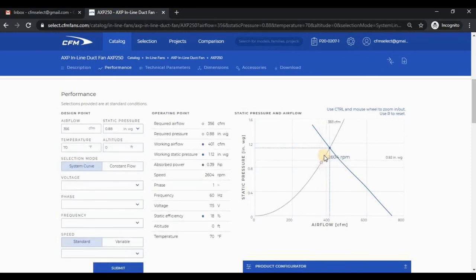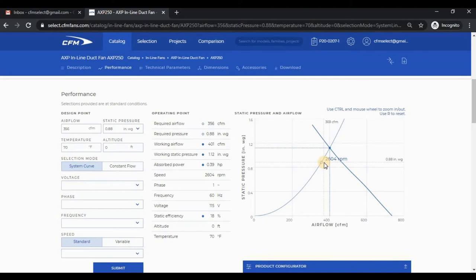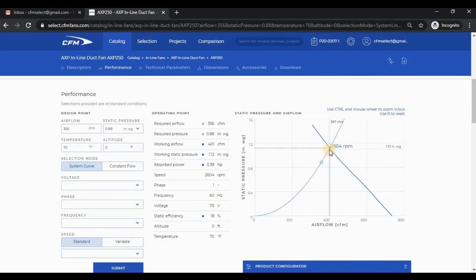The unfilled circle is the required point, but since the speed is set to standard, meaning a speed control is not used, the operating point ran up to the intersection between the system and fan curves. Let's say that the required airflow point is the point that we absolutely need.